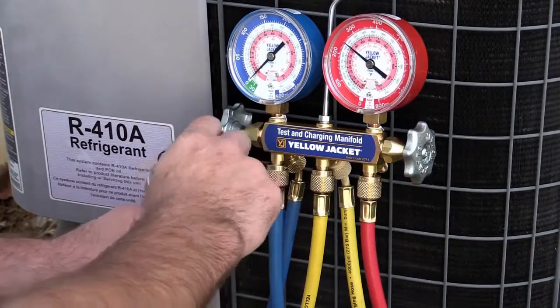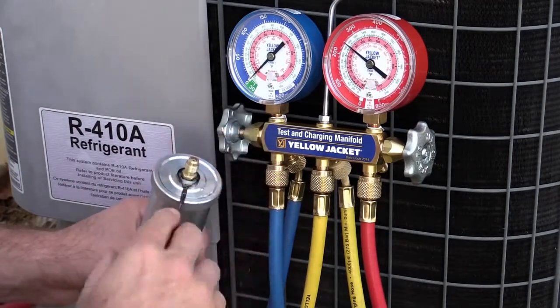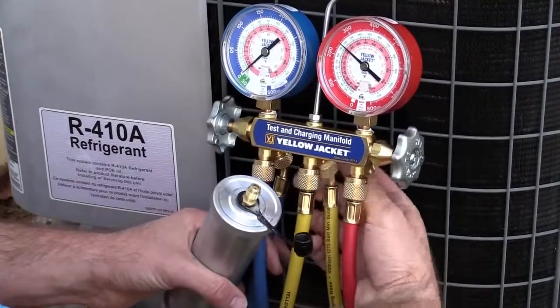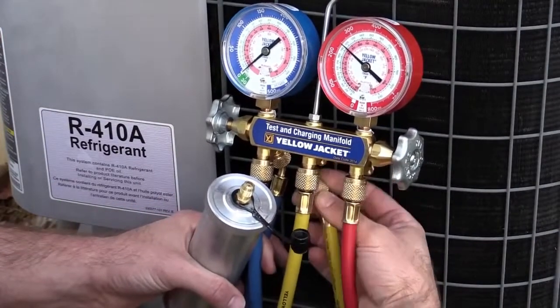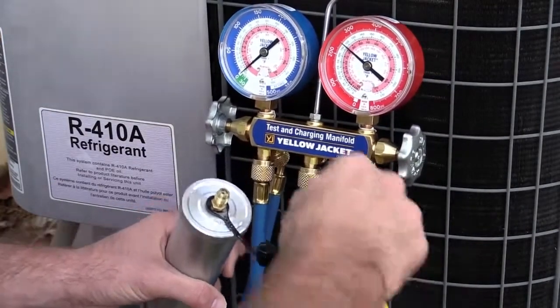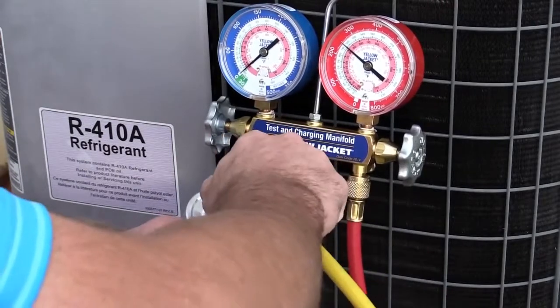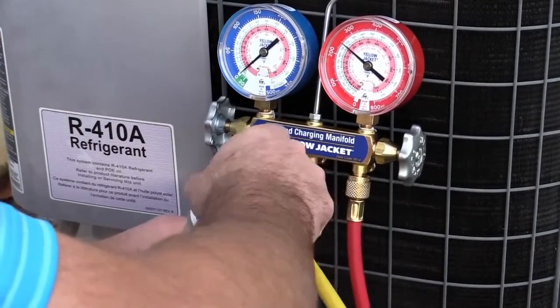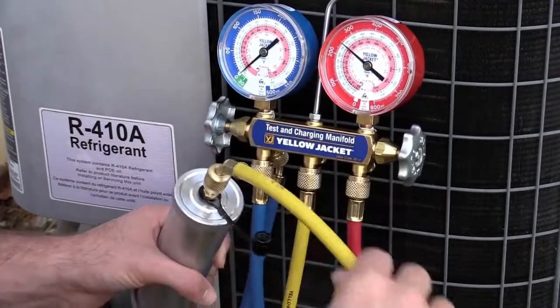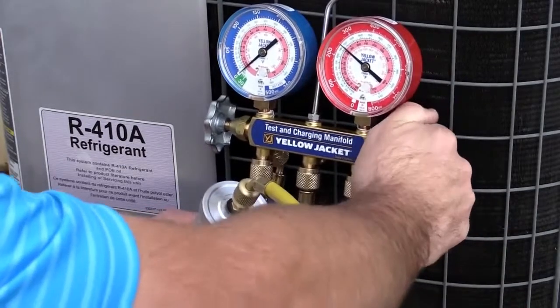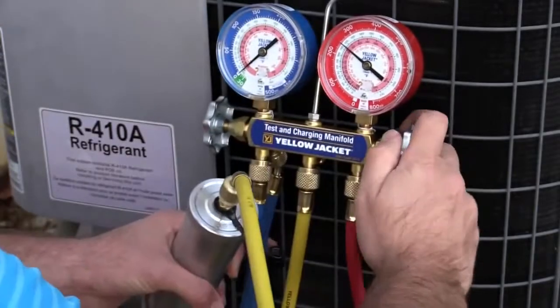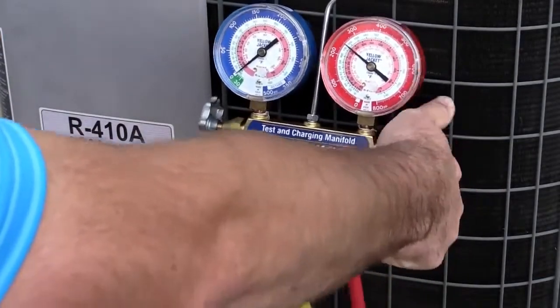Remove the protective cap from the Schrader fitting and barely thread the middle yellow manifold hose to the 1/4" male inlet fitting of the AC Renew injector tool. Be very careful as to not depress or otherwise engage the Schrader core. Briefly crack open the high side manifold valve to purge air from the yellow hose, then quickly tighten the loose yellow hose fitting at the injector and close the high side manifold valve.